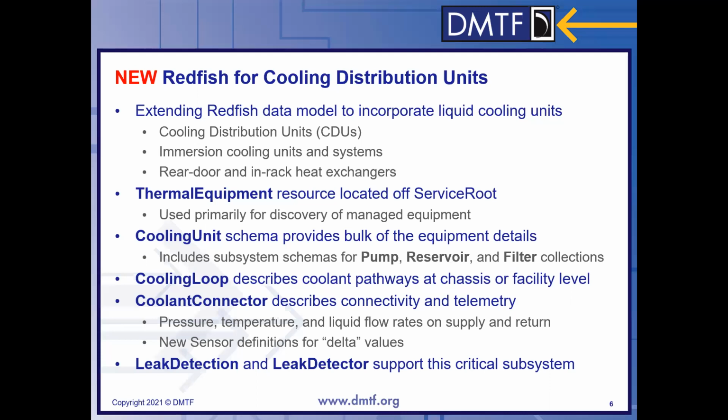So you can have a gateway device, for instance, that would manage a whole row of individual CDUs that maybe are daisy chained or connected via Modbus or whatnot to one device that surfaces the web interface. All of that is supported. So you can have 5 cooling units all managed from a single IP address. That's all just part of normal Redfish modeling semantics.